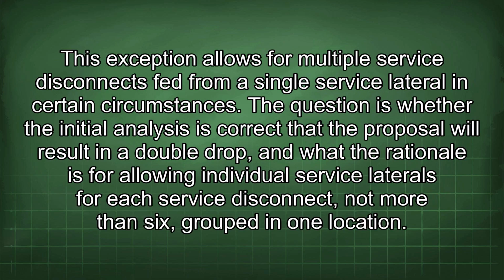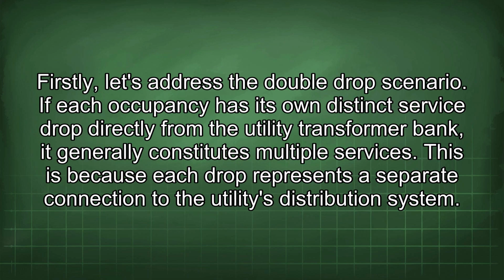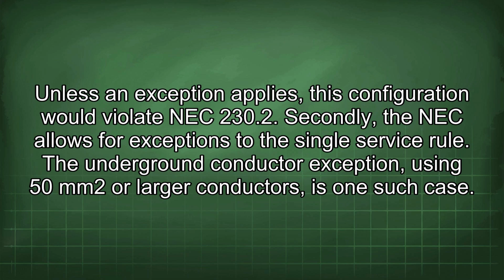This exception allows for multiple service disconnects fed from a single service lateral in certain circumstances. The question is whether the initial analysis is correct that the proposal will result in a double drop, and what the rationale is for allowing individual service laterals for each service disconnect, not more than 6, grouped in one location. Firstly, let's address the double drop scenario. If each occupancy has its own distinct service drop directly from the utility transformer bank, it generally constitutes multiple services. This is because each drop represents a separate connection to the utility's distribution system. Unless an exception applies, this configuration would violate NEC 230.2.